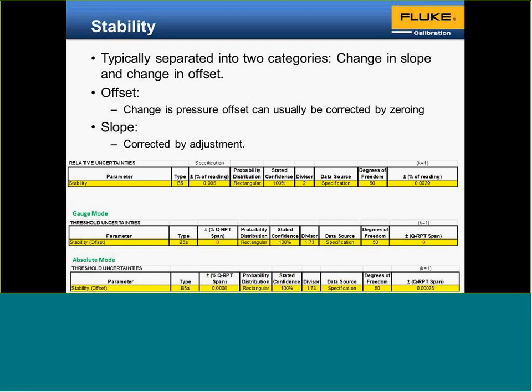We have the Q-RPT categorized into two parts: long-term stability and short-term stability. Long-term drift of the sensor and or the electronics is monitored by interim checks, but corrected by adjustment. Short-term stability is zero drift, which can be addressed by zeroing the instrument if you're in absolute mode, and in gauge mode you can zero when you're vented, and that gets rid of any zero influence.